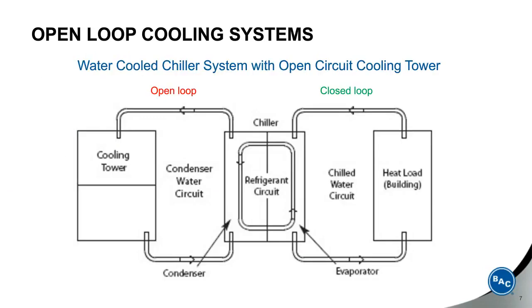Now, here's a typical open-loop cooling system, which is based on a water-cooled chiller with an open-circuit cooling tower. You see in the center there is the chiller and the chilled water circuit that is removing heat from the building, the heat load from the building. Now, that chilled water circuit is a closed loop. On the other hand, on the other side, where the condenser of the chiller is, we have an open loop. The water from the cooling tower is pumped through the chiller condenser. It picks up heat and returns to the cooling tower to be cooled.